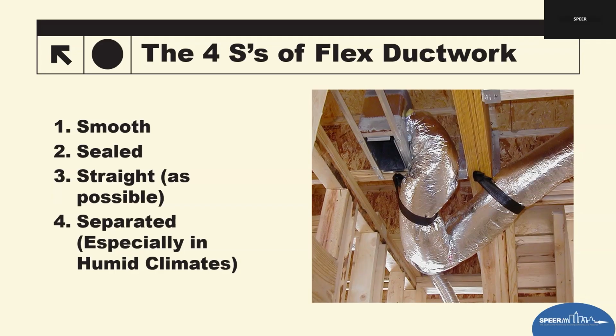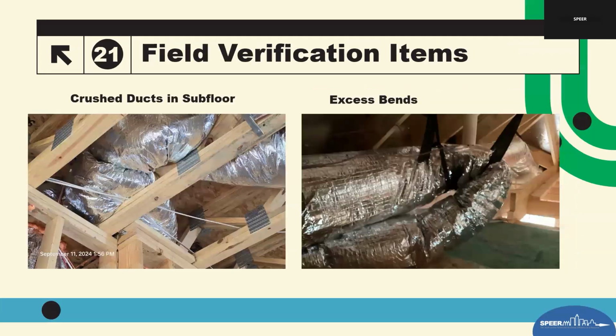It should be separated, so as not to gain or lose conditioned air inside the duct due to conductivity through the duct itself. So this is what we talked about earlier, just looking at ductwork. So, running through subfloors, I know it's in conditioned space. We're not really looking for it to be insulated, but they're using the same flex duct they do in the attic, and then they're trying to cram it through a small opening in a truss floor system, or even TJIs, and they're trying to drill holes and cut through it and cram the duct between it.